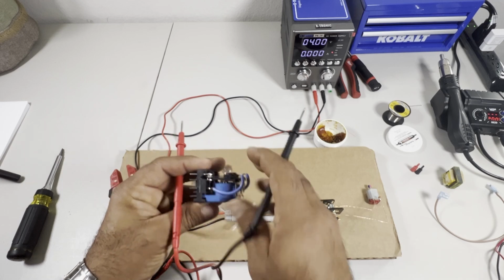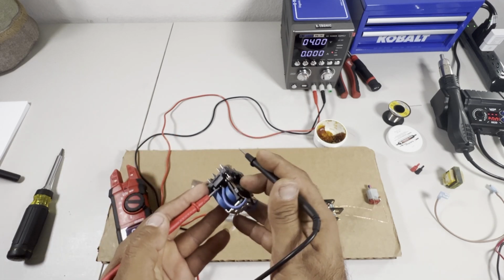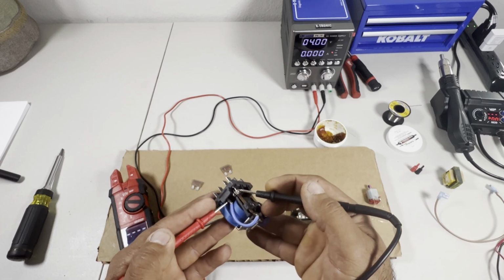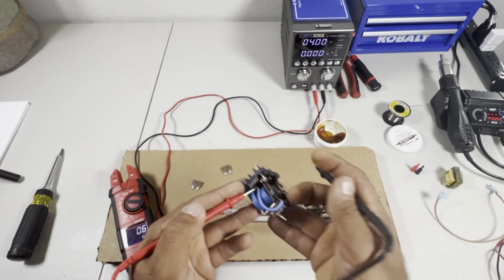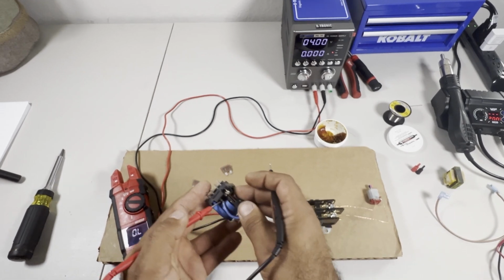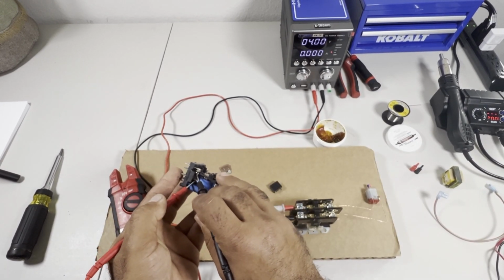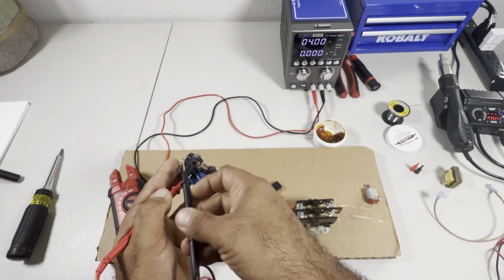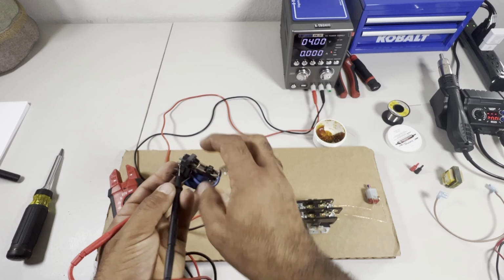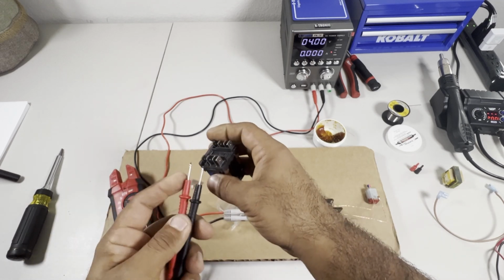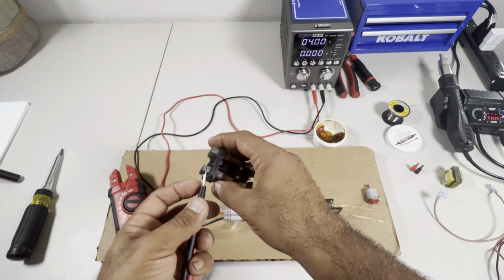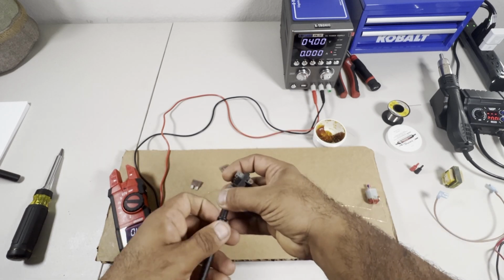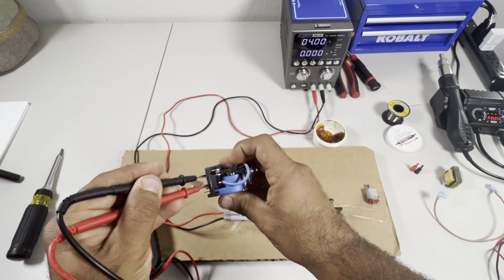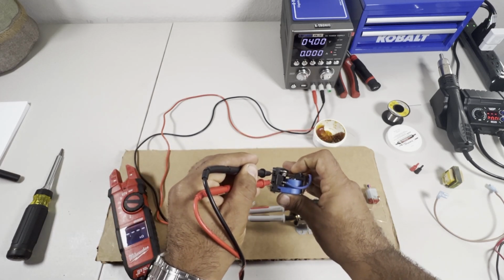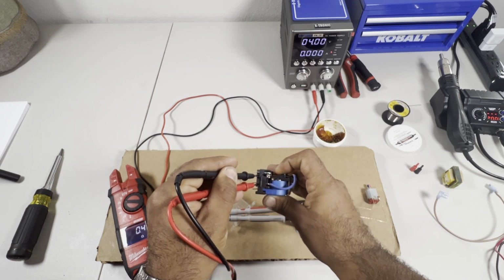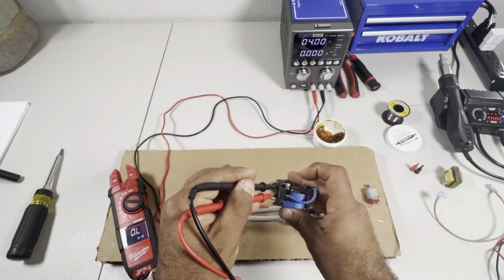That's what is called normally closed, because when you check it right now with no power to the coil, it is 0 ohm, and the other one is normally open. Sorry. And when you check this one right now, there is nothing. Now, if I'm able to get these two together at the same time with one hand and push on this contactor to close it, you can see now the ohm meter shows 0 to that leg. And when I let it go, it goes to OL, infinity.